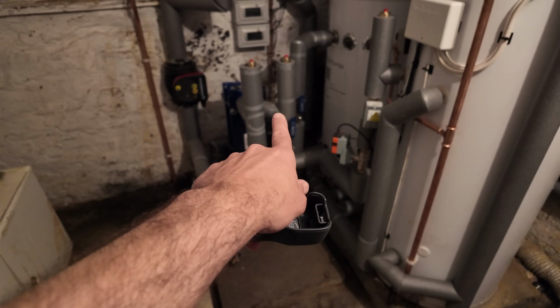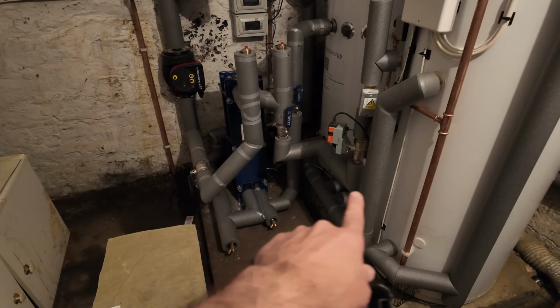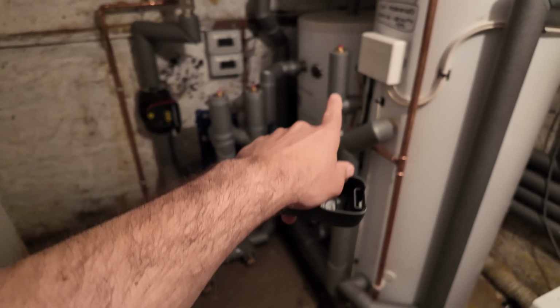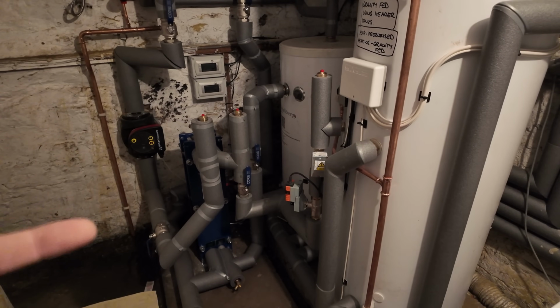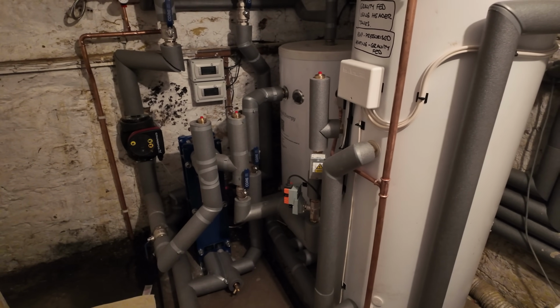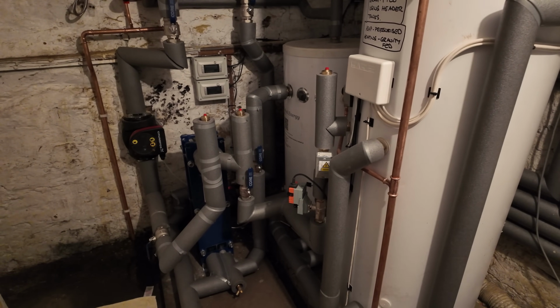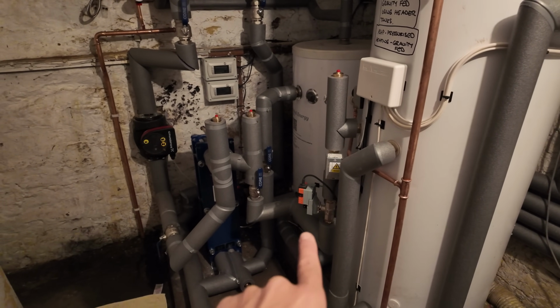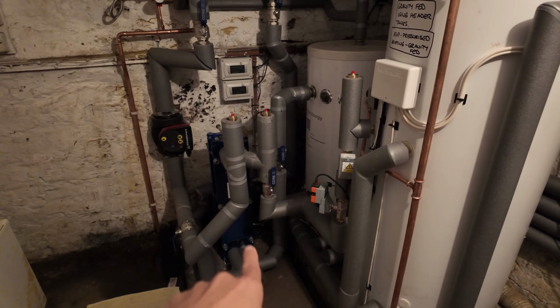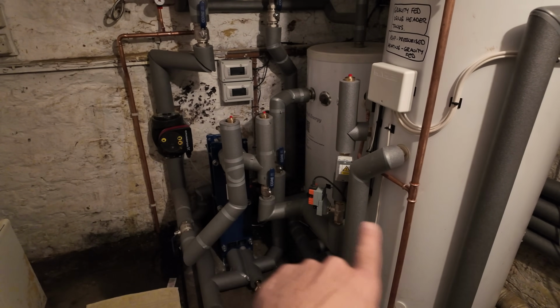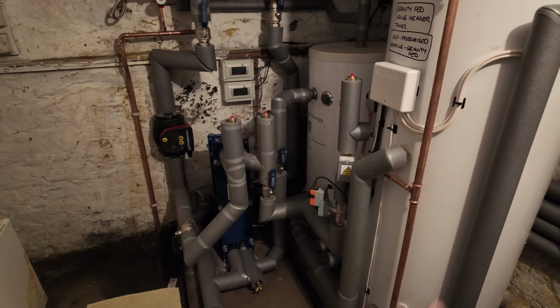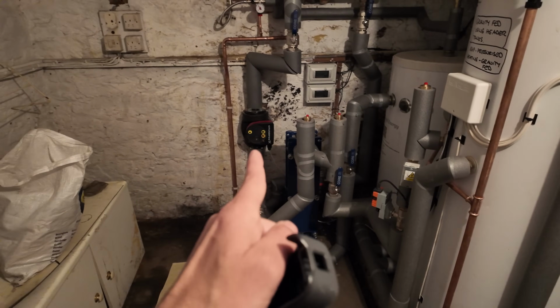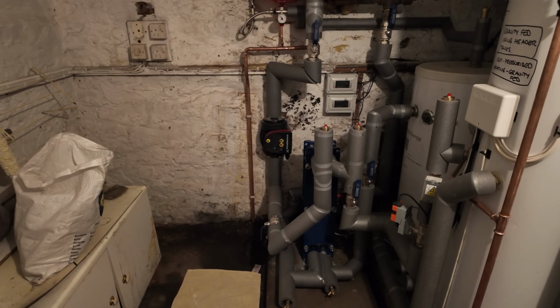And then straight into the heat exchanger, yeah? And then back to the heat pumps via the volumizer. So we've no distortion there, okay? So it's a cascade, but we've combined the pipe work so we don't get distortion, and we've piped straight to the heat exchanger, back via the volumizer to the heat pumps. And then the distribution side is off that honking big pump there.